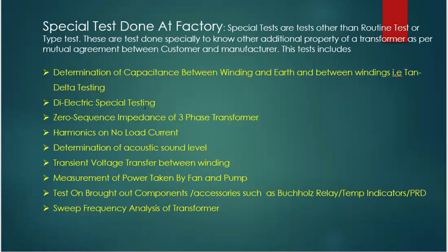Dielectric special testing, zero sequence impedance of a three-phase transformer, harmonics of no load current, determination of acoustic sound level, transient voltage transfer between the windings, and measurement of power taken by fans and pumps. Tests on transformer accessories such as Buchholz relay, temperature indicator, etc. are also performed as a part of the special testing. Sweep frequency analysis is also a special testing of a transformer. Now, having described all the test procedures, I will cover these test procedures one by one.